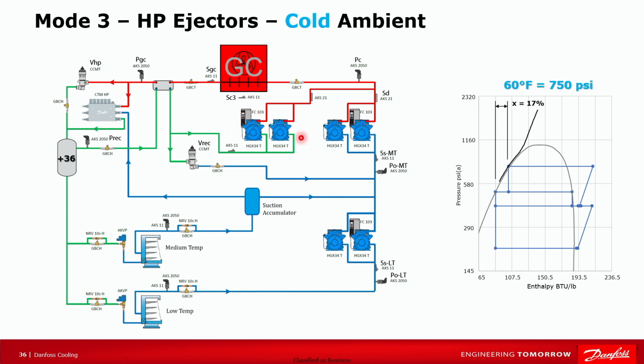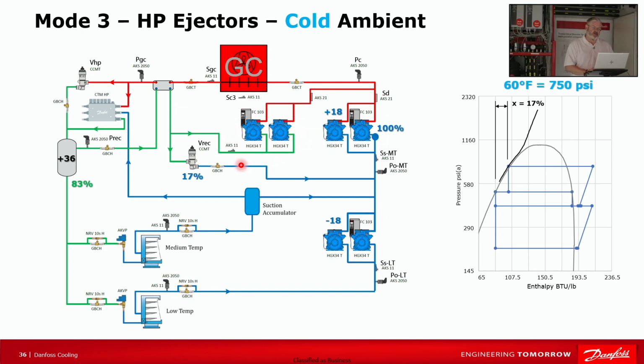So again, much like the parallel compression option, you paid for all of this. It's a 60-degree day. It's not really going to do anything for you. We only got 17% flash gas at 60 degrees, and we already know that's not enough to run the parallel compressors, and we're okay running it on the medium temp because of the efficiency we get from CO₂ as a refrigerant. So on that 60-degree day, you're going to get 100% of your load still going all to just the medium temp compressors, not using the parallel compression at all.